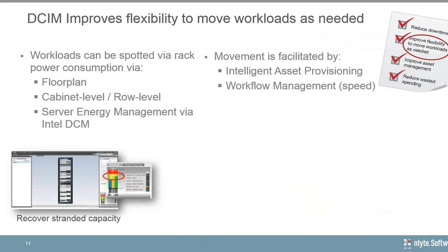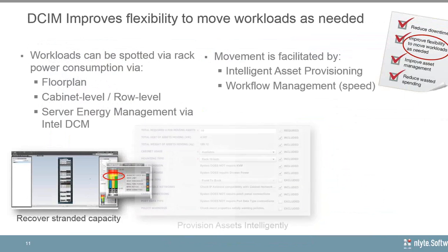And the reason that's important is because of the virtualization, most people think of, oh, well, I can get the servers to take on more workload. But servers, while they do consume power individually, it's the limitation of the rack that has power. And so that rack level power is what needs to be measured. You might be hitting a rack power threshold first. And so that's when you say, okay, I've got to move this workload, even virtually, to another elevation of cabinet because I'm hitting that threshold. And that's the flexibility that a DCIM can help you with.